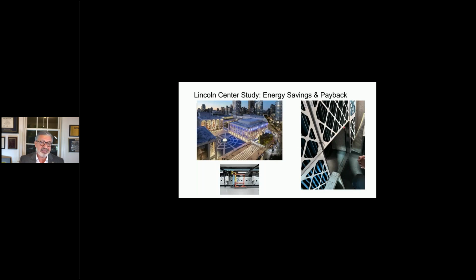The test is underway, but modeling has shown that when you calculate energy cost over 10 years compared to non-thermal plasma, the same could be done with ionization, the costs are tremendously different. A MERV 16 filter over 10 years will cost almost $100,000 in electrical costs, based on this data, compared to $9,000. I believe ionization might even be less, but I'm not sure.